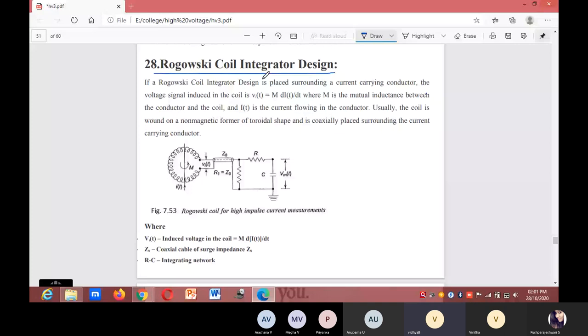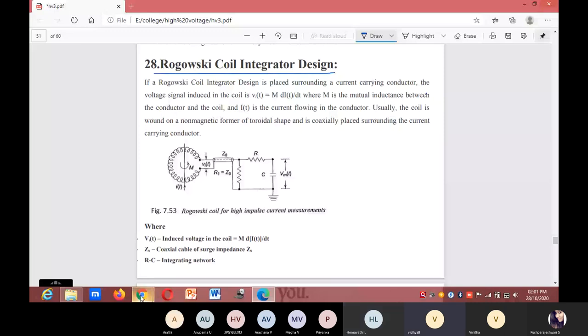It consists of a helical coil of wire with a lead from one end returning to the center of the coil to the other end, so that both terminals are at the same end of the coil. This Rogowski coil is a toroid of wire used to measure an alternating current through a cable encircled by the toroid.